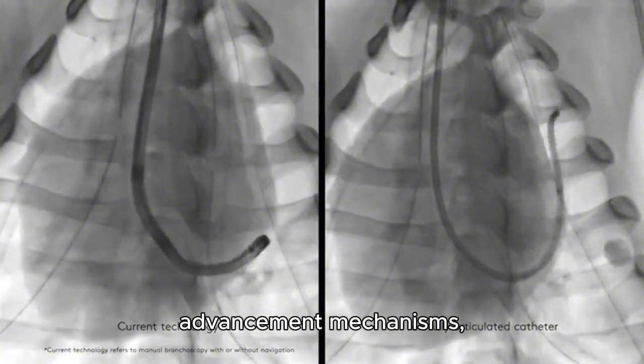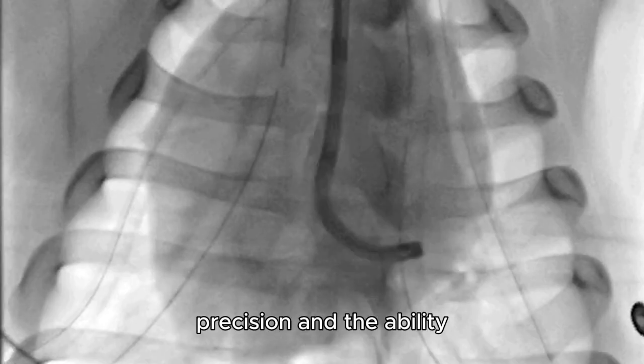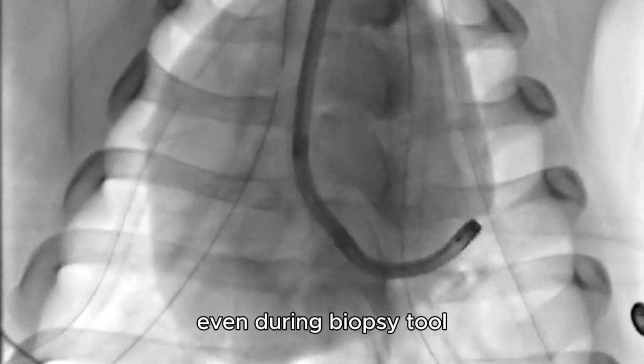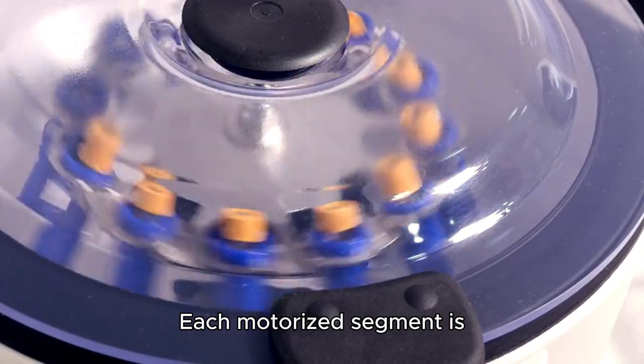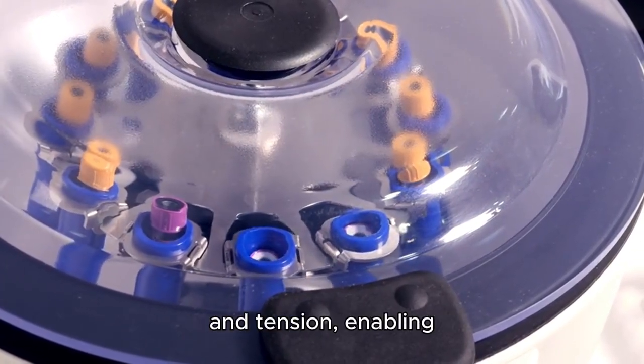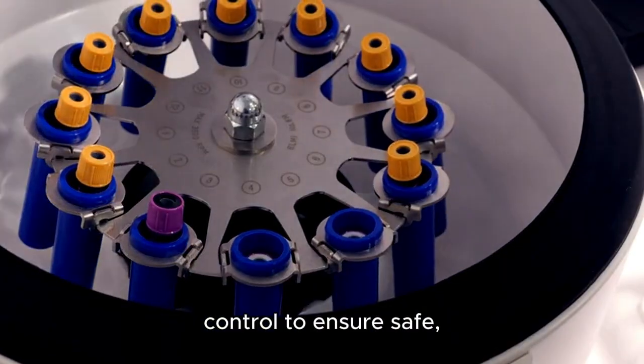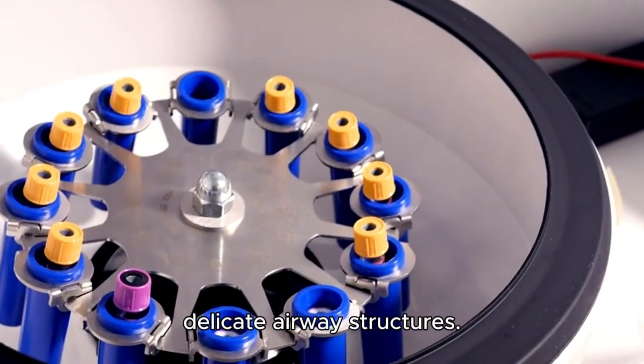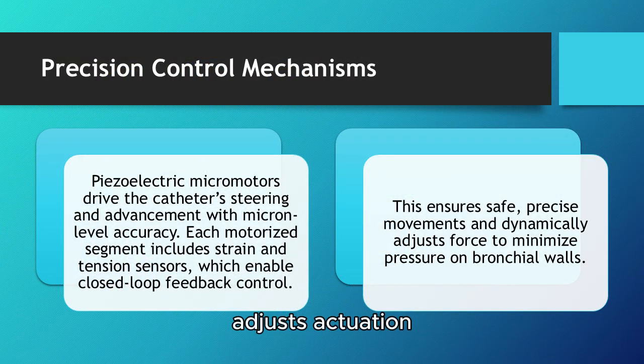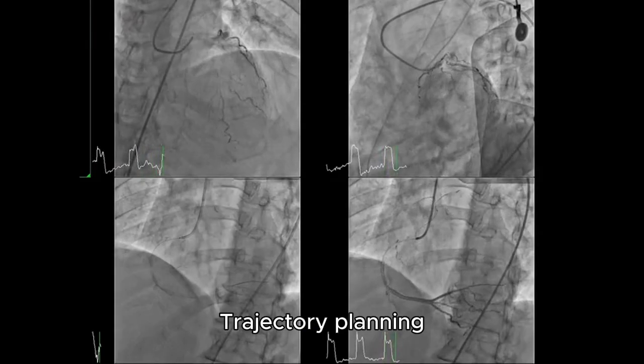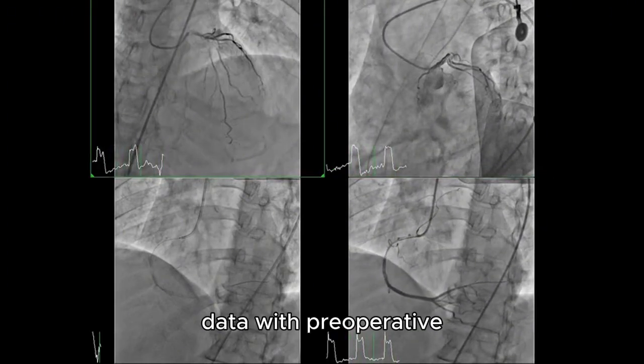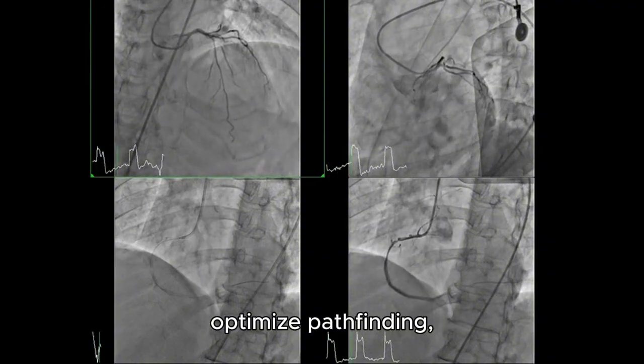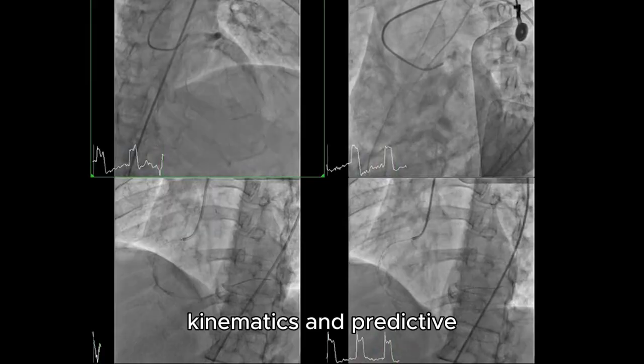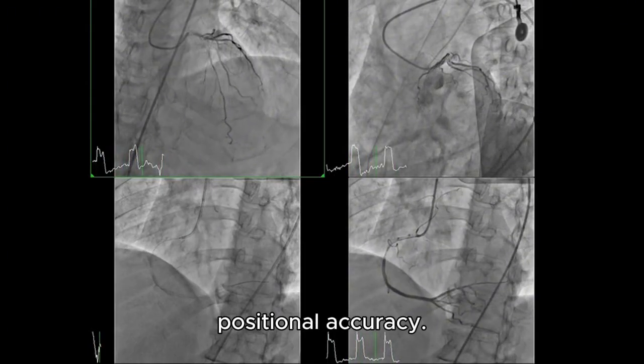Piezoelectric micromotors drive the steering and advancement mechanisms, providing micron-level precision and the ability to maintain stability even during biopsy tool deployment. Each motorized segment is equipped with localized sensors that monitor strain and tension, enabling closed-loop feedback control to ensure safe, accurate movements within delicate airway structures. The system dynamically adjusts actuation forces based on real-time feedback to prevent excessive pressure on bronchial walls, reducing the risk of mucosal injury. Trajectory planning algorithms integrate real-time catheter shape data with preoperative CT-derived airway maps to optimize pathfinding, employing inverse kinematics and predictive modeling to minimize deviation and maintain positional accuracy.